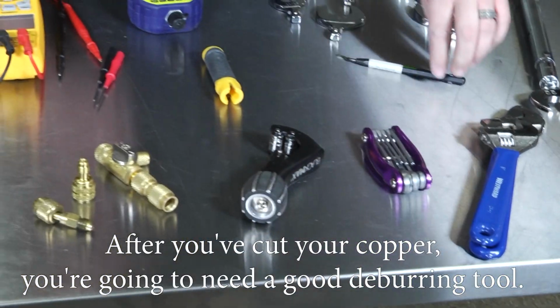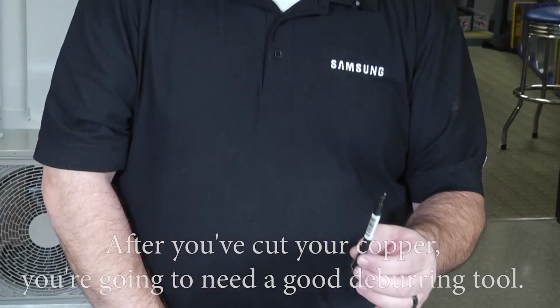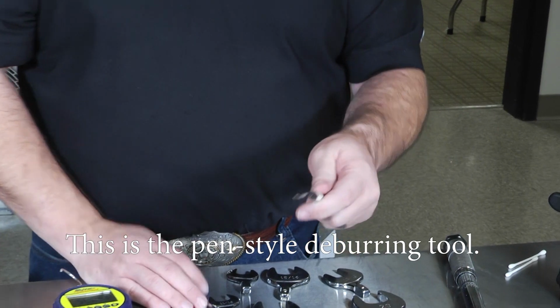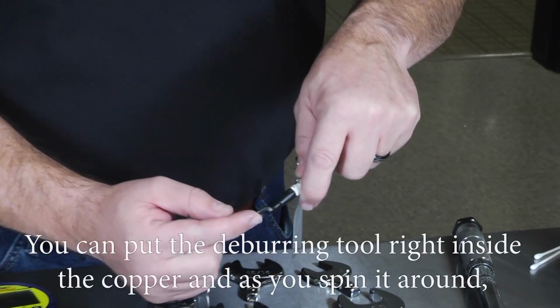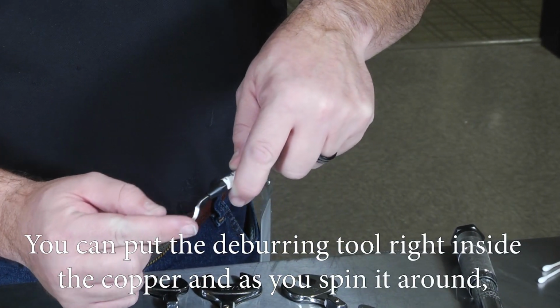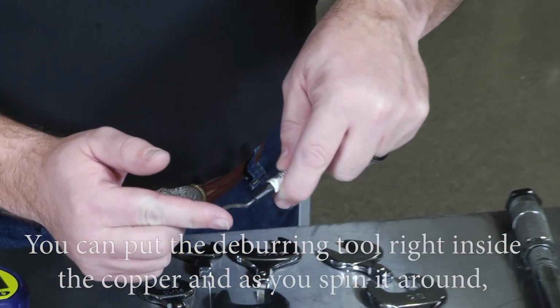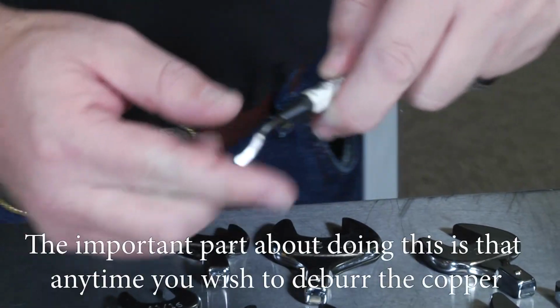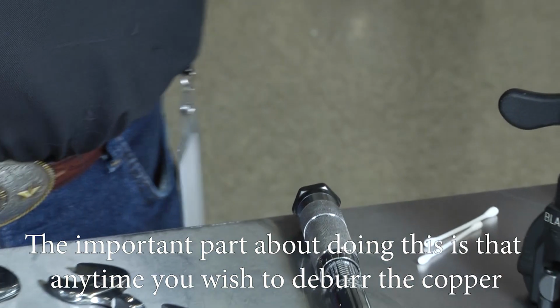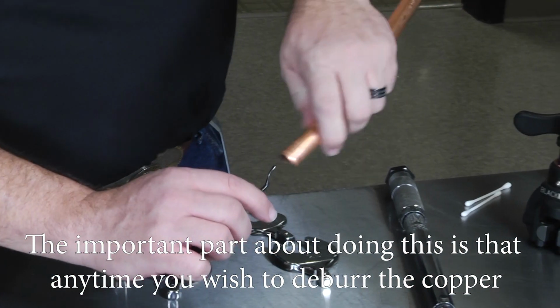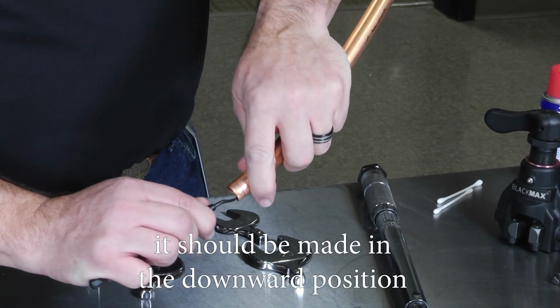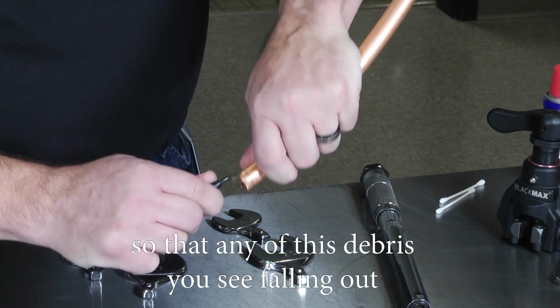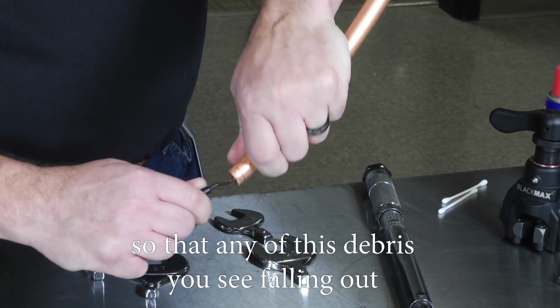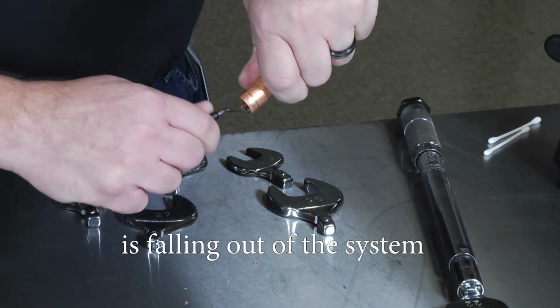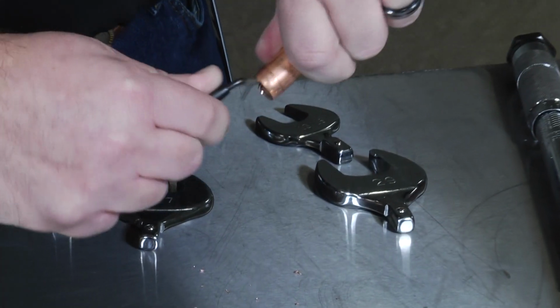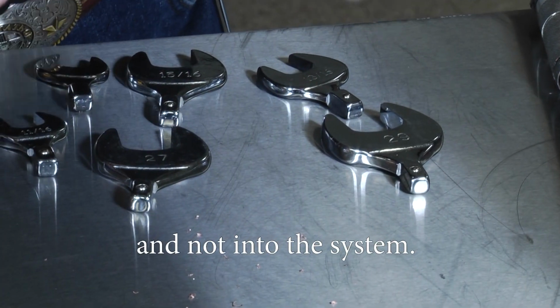After you've cut your copper, you're going to need a good deburring tool. This is the pen style deburring tool. You can put the deburring tool right inside the copper, and as you spin it around, it'll shave off any nicks or burrs. The important part about doing this is that anytime you wish to deburr the copper, it should be done in the downward position so that any of this debris that you see falling out is falling out of the system and not into the system.